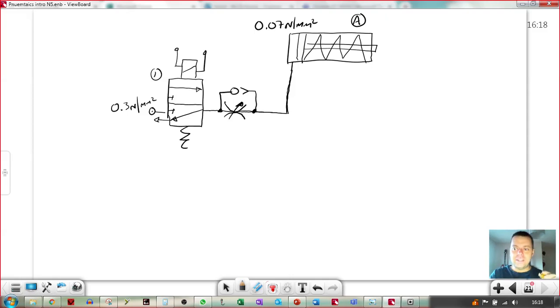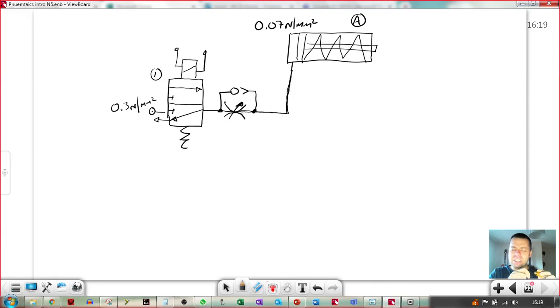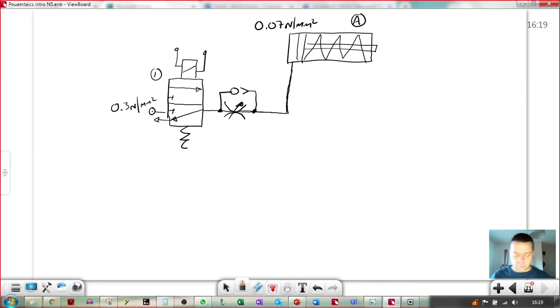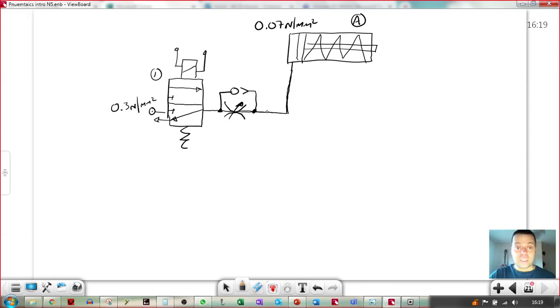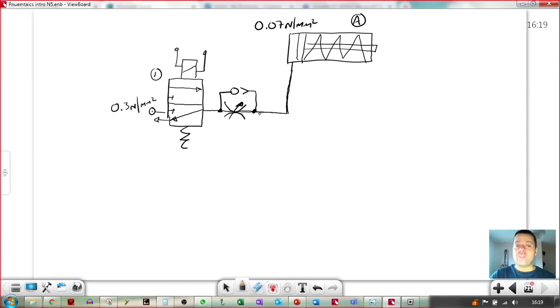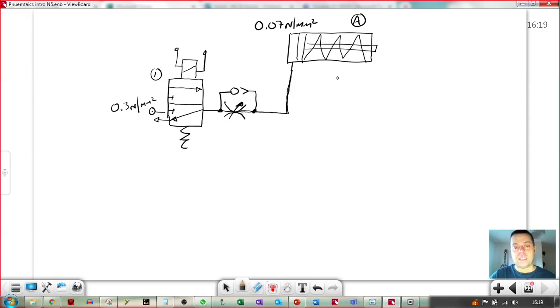And it gets to the point where suddenly it's given you restriction and even the slightest turn in the screw gives you massive amounts of flow restriction. So they're quite difficult to use in that respect. If you haven't used them, it's just experiential. So what would happen here is, even with quite a lot of restriction, you'd find it difficult to get a measurable time delay, like a 3 second time delay.